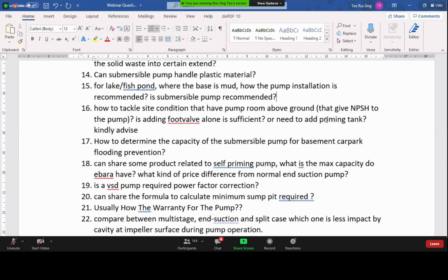But you have to let us know. Question 16: how to tackle site conditions that have the pump room above ground, which affects the NPSH to the pump? Is adding a foot valve alone sufficient, or do we need to add a priming tank? Okay, very good question. You are asking about a negative suction application, which means that the water is below the pump.